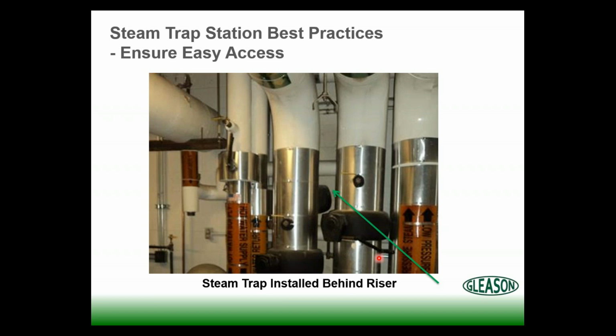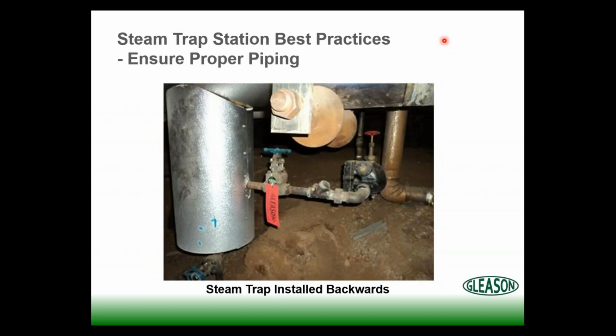So let me backtrack a little bit. Notice here I said steam trap station best practices. When we look at a steam trap, we don't look at the steam trap only. There's so much more to it than that. We look at the entire steam trap station. How is it piped? Is it the right steam trap for the application? Is it installed upside down or backwards? Many different things play into a proper steam trap station installation, so we need to pay attention to that. So we want to make sure we can install these where we can get to them and service them.